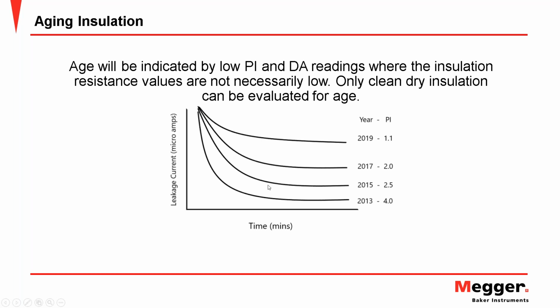So again, by evaluating that change in insulation and the insulation's ability to polarize, we can have an assessment of whether it has good mechanical integrity or not. But again, that requires a clean and dry environment. Unfortunately, we don't have that in the field, so this is a test that's primarily reserved for an age evaluation process in a shop. However, the PI and DA, as I showed you in the previous slide, are used as a qualitative assessment of the infiltration of contamination or moisture into our circuit response.